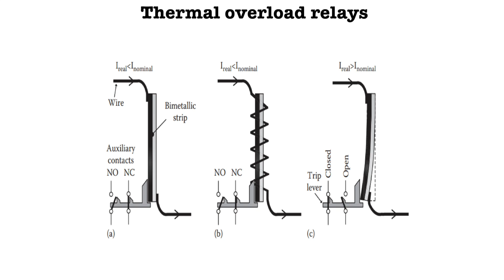In three-phase systems, the thermal overload relays typically include three bimetal strips, each monitoring one phase. This design allows the relay to detect not only overcurrent but also phase imbalance or losses. These relays cover a range of motor currents and can be adjusted to match the specific requirements of different motors.